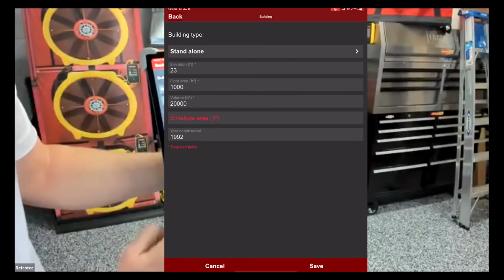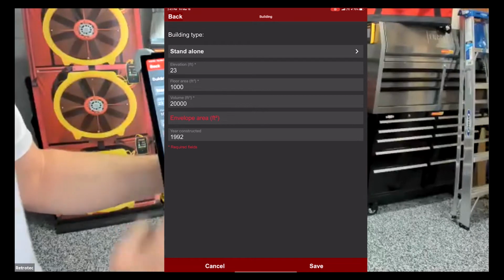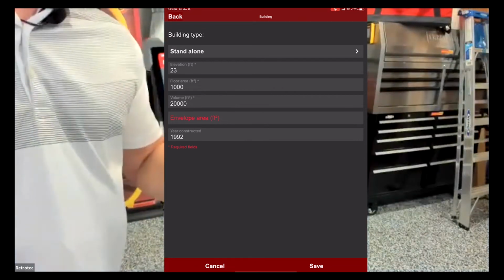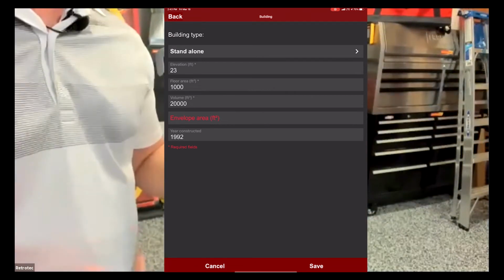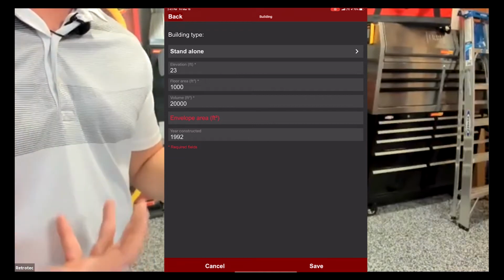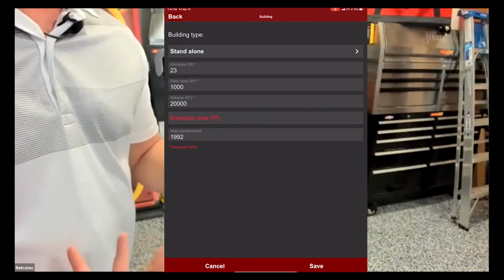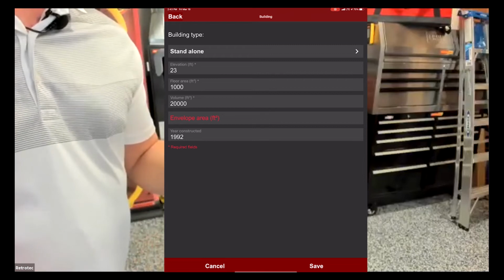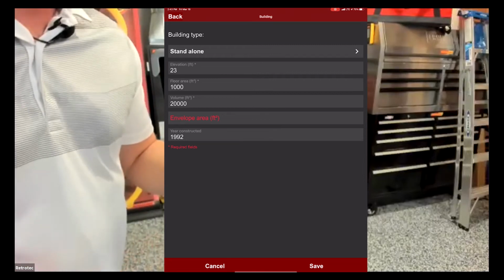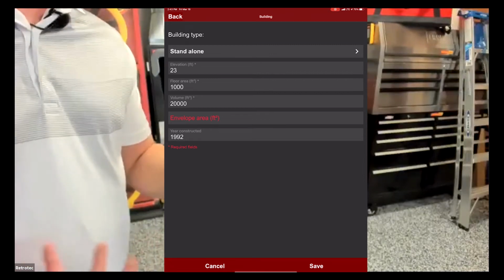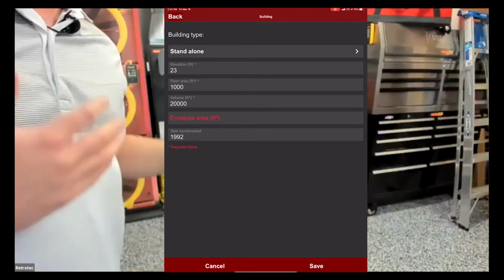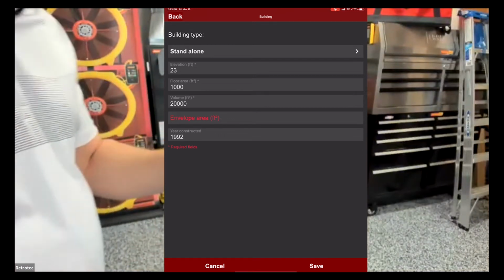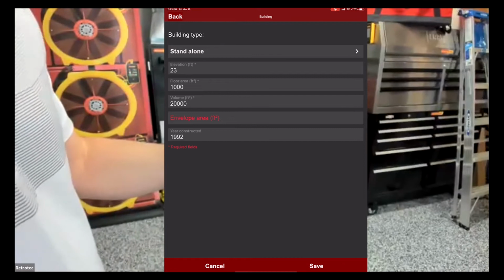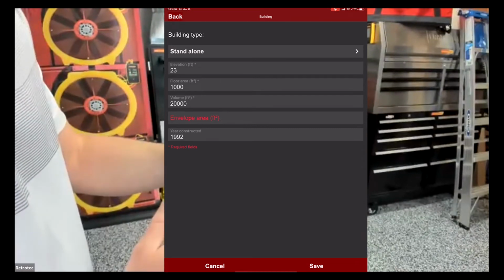And that's another thing too - if the house has multiple systems, you're not going to put the house square footage, you're going to put the square footage that system is serving. So if it's a 2,000 square foot house, hopefully it doesn't have 2 systems - usually it doesn't need it, but it happens. If 1,000 is dedicated to one, then you put in 1,000 for the area that system serves.